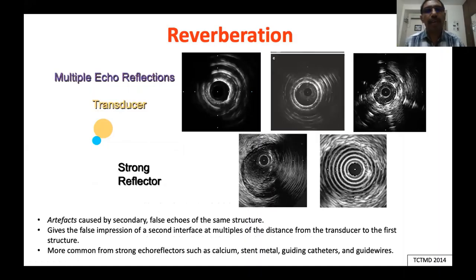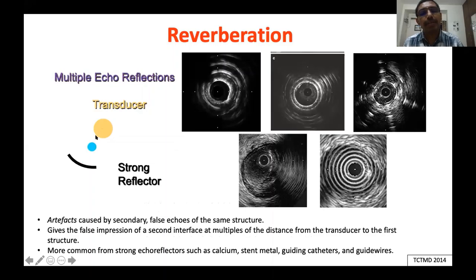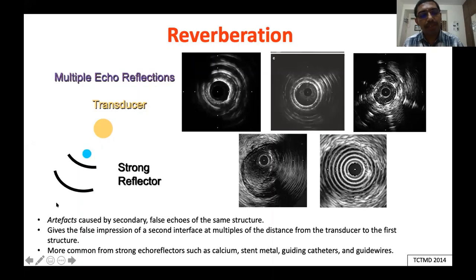Reverberation is nothing but repeated reflections between the catheter and a highly reflective surface, such as a metal stent strut or calcium. The system counts each reflection as having traveled additional multiples of the depth — if it travels twice, it appears at twice the distance, forming a ghost image; if three times, a ghost image at three times the distance. The clinical importance: you should not mistake these ghost images for different interfaces. One interface of calcium can produce reverberation of multiple interfaces — these are all ghost shadows.